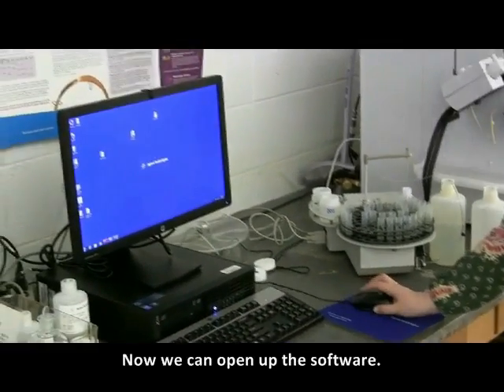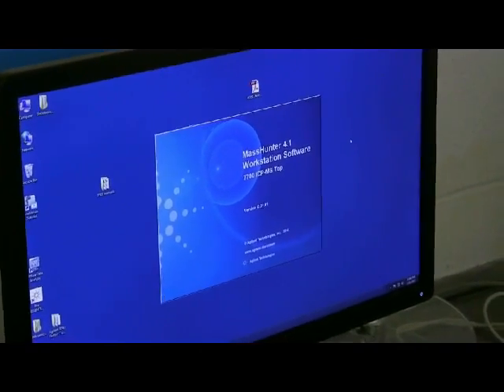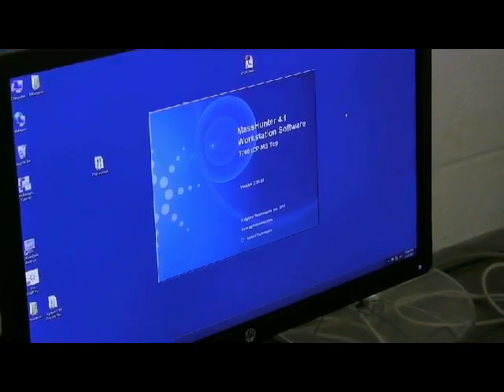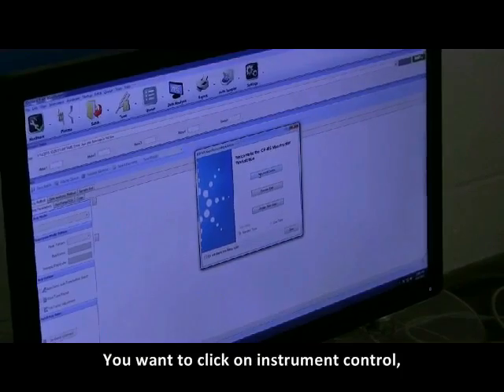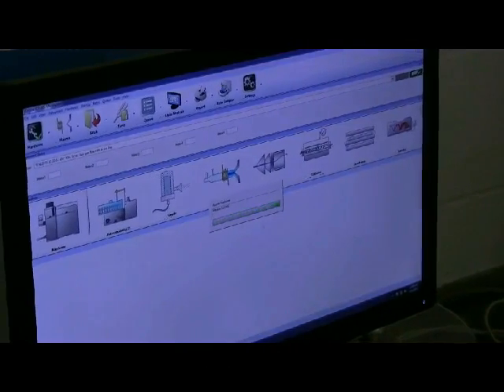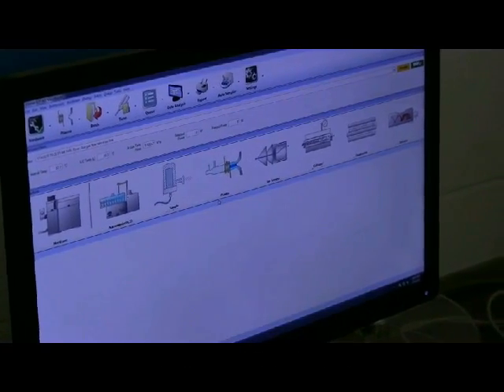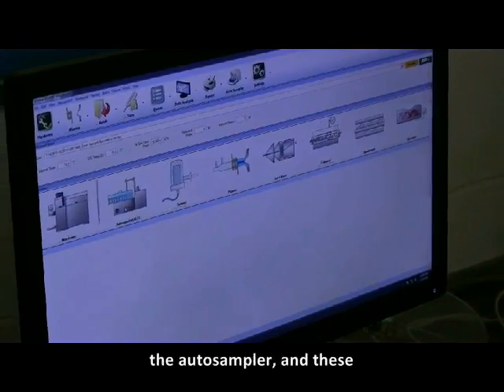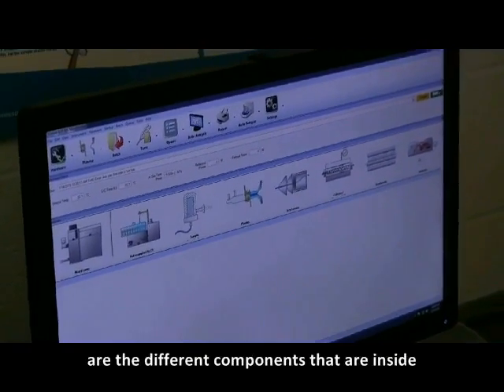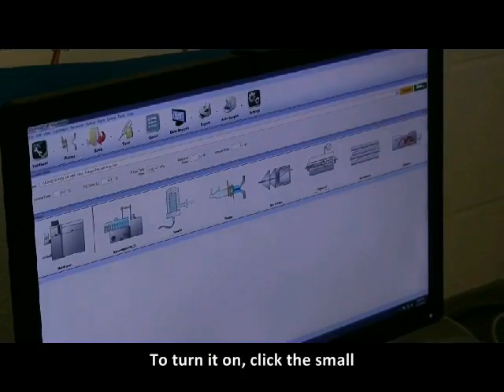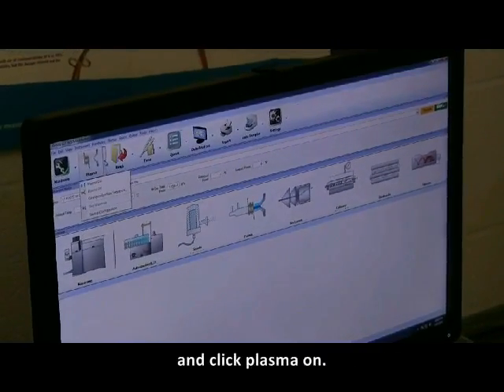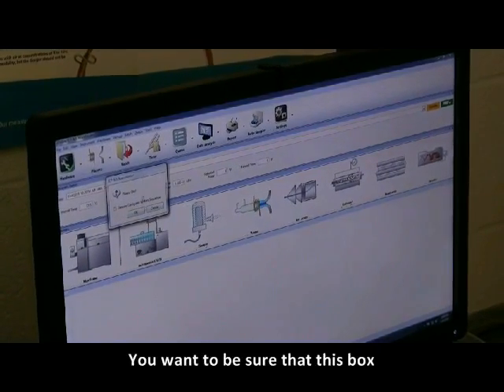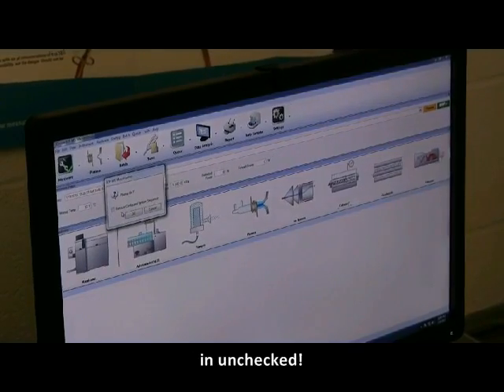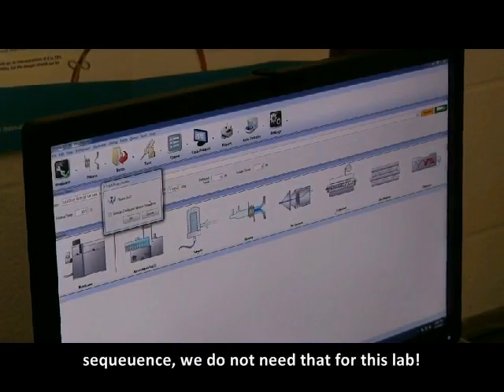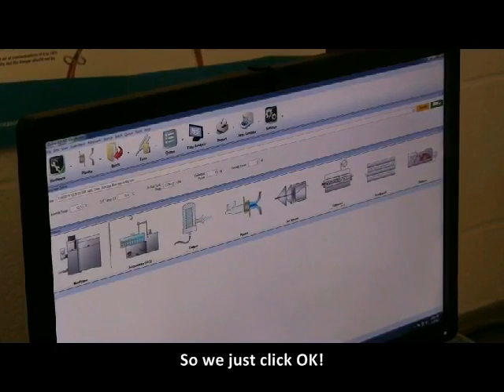Now we can open up the software, ICPMS Instrument Control. You want to click on Instrument Control, and you'll see it's initializing. Here you can see the ICPMS, the autosampler, and the different components that are inside the instrument. To turn it on, click the small black arrow next to plasma and click plasma on. You want to be sure that this box is unchecked. It says execute configured ignition sequence. We do not need that for this lab. So we just click OK.